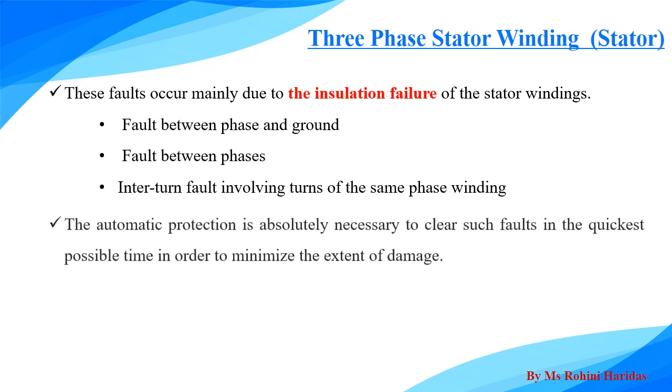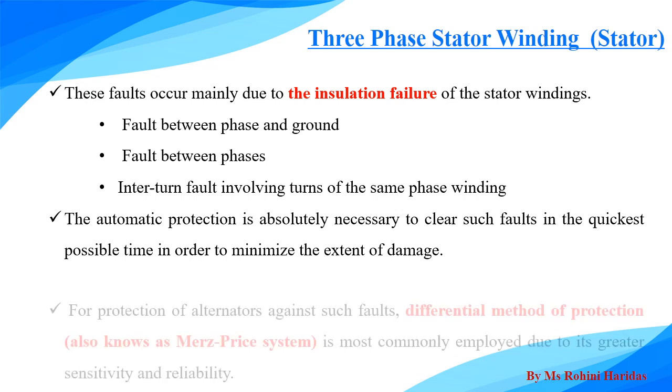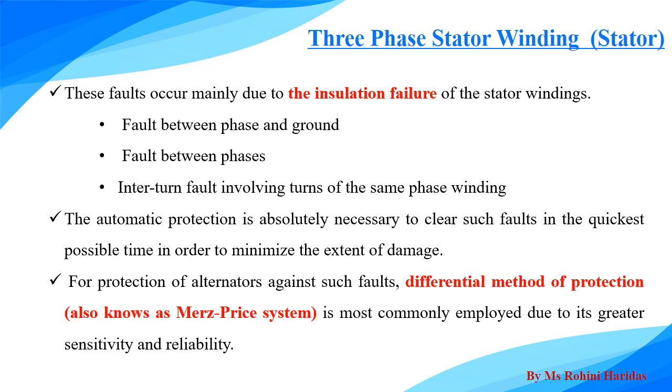The stator winding involves the armature winding and therefore, the automatic protection is absolutely necessary to clear such faults in the quickest possible time in order to minimize the extent of the damage. For the protection of the alternator against such a fault, we prefer the differential method of protection. It is also known as Merz-Price system and it is commonly employed due to its greater sensitivity and reliability.